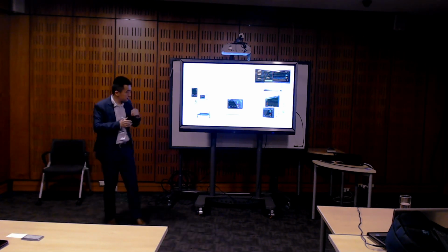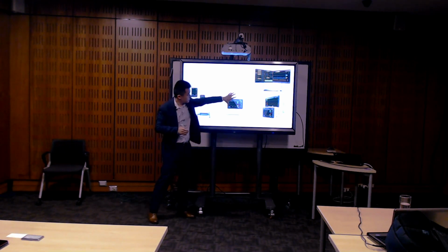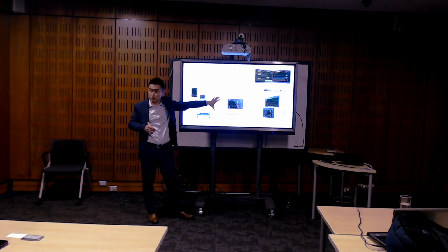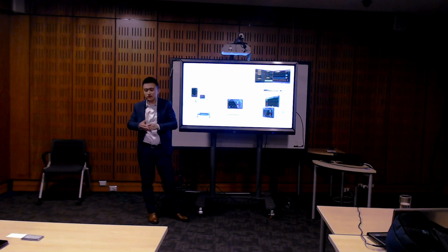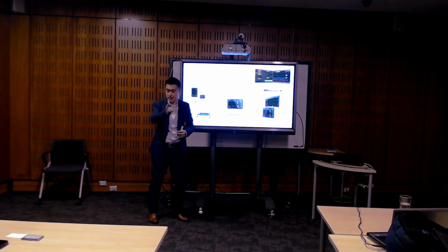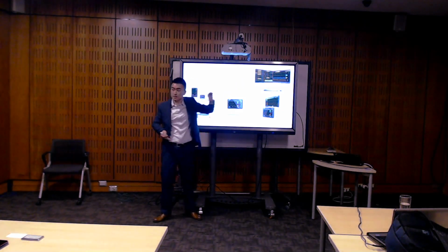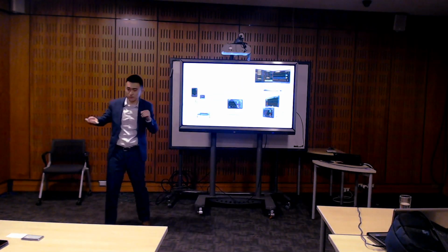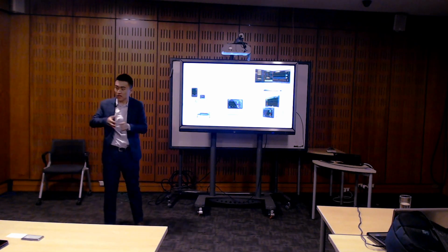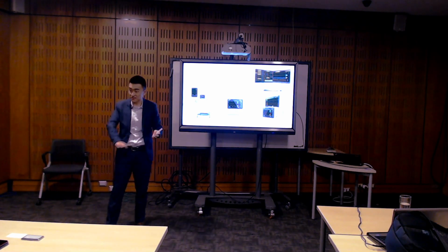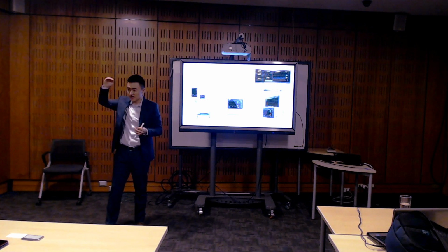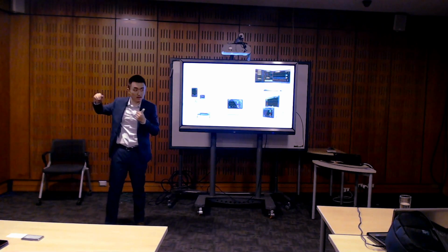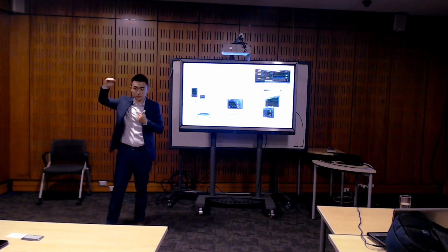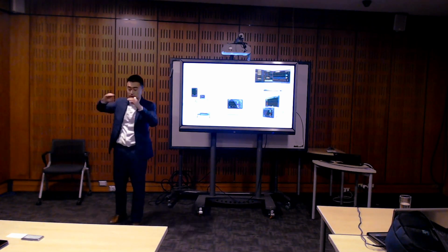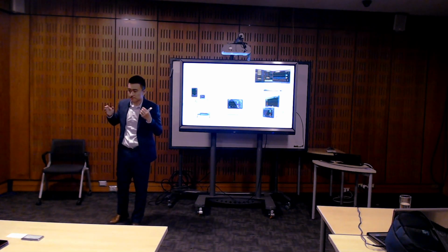Sometimes during the transport, if I lose connection to the Wi-Fi, and after 5 hours I reconnect, the data is uploading to the central station. But this also depends on whether the network is busy or not, because the priority of backfilling is low. The high priority is the real-time waveform and alarms. So depending on the data flow and the quality of the network, it will take more or less time.